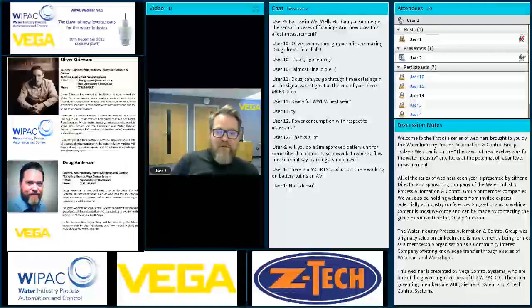It is technically possible, and we have done it in some applications, but to be honest, I think the costs are too high. So we would quite like the opportunity to look at getting an MCerts product for a standalone transducer, or at least one that could input into a proprietary battery powered telemetry unit. We can offer an SDI 12 device that's got programmable flow curves inside it that could go straight into your data logger, and the data logger could be doing the logging and the transmission of the data. But at the moment, it's not allowed for a level sensor doing open channel flow measurement to be used without a control device.